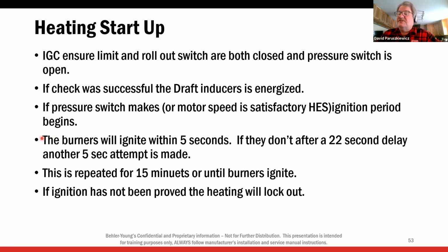So again, igniter starts, gas valve opens, 5 seconds, no flame proof, shuts, waits 22 seconds. It's going to try again in 22 seconds. Igniter starts, gas valve opens. And if it ignites within 5 seconds, we continue. If not, it drops out and waits another 22 seconds. This trial for ignition will repeat 15 minutes or until burner ignites. So it'll continue to retry for 15 minutes and then it will lock out. So if the ignition has not been proved, the heating will then lock out.